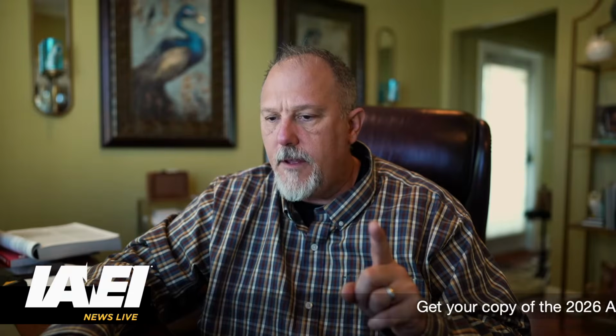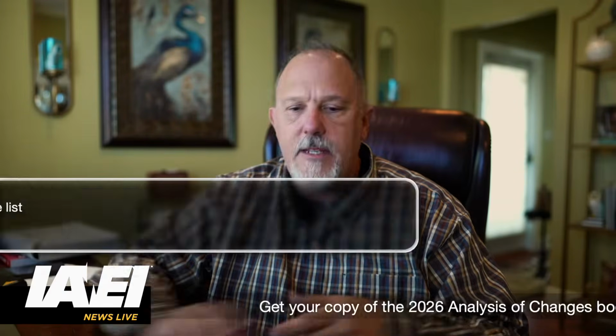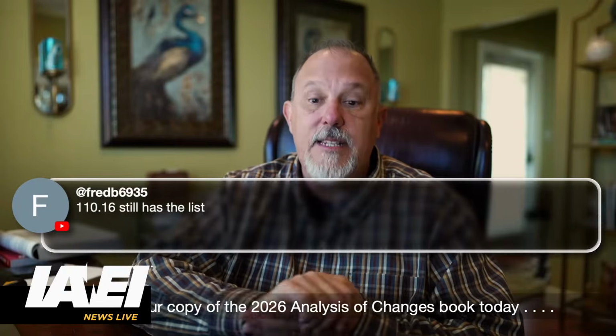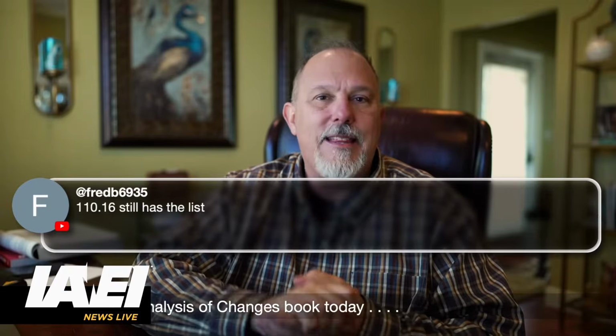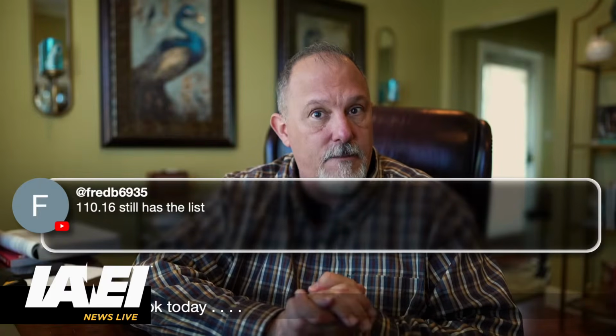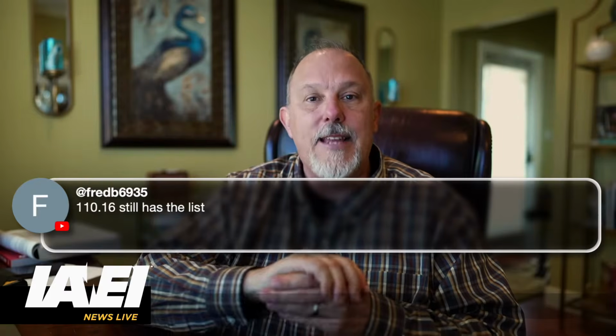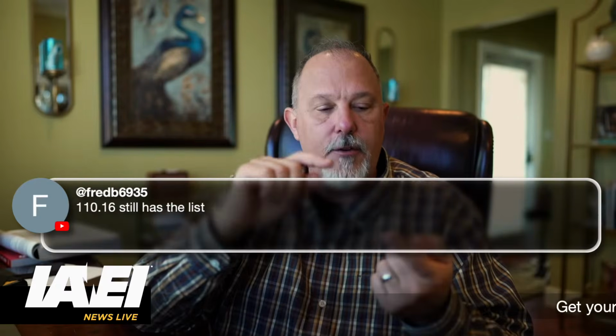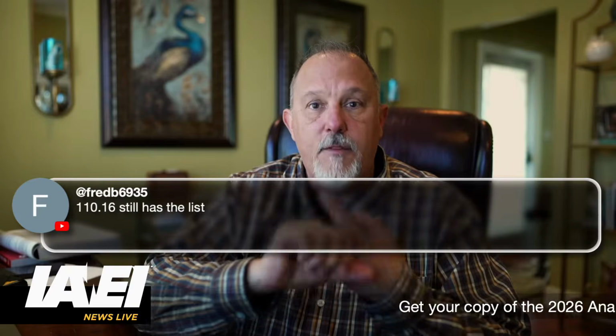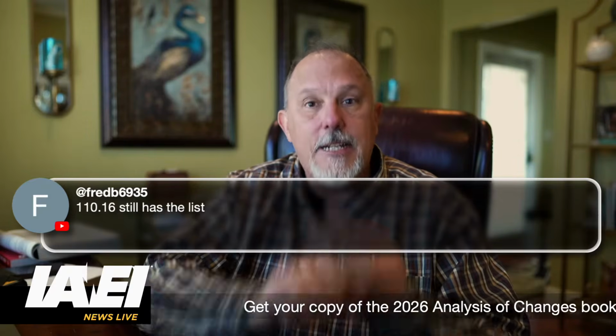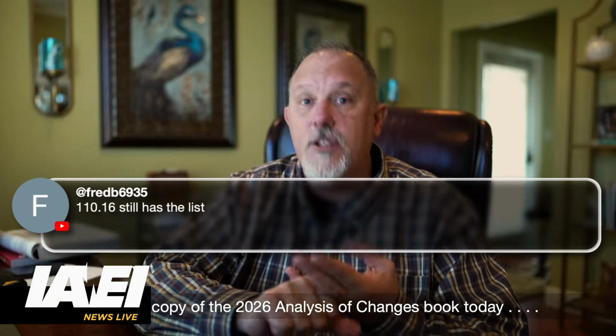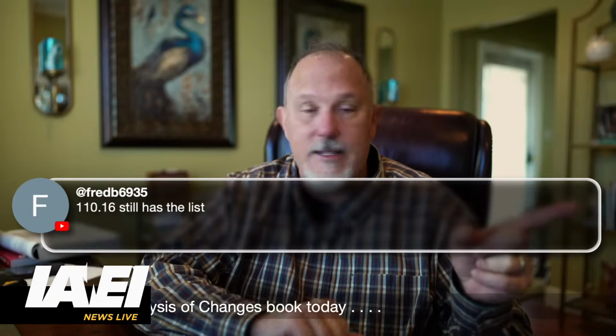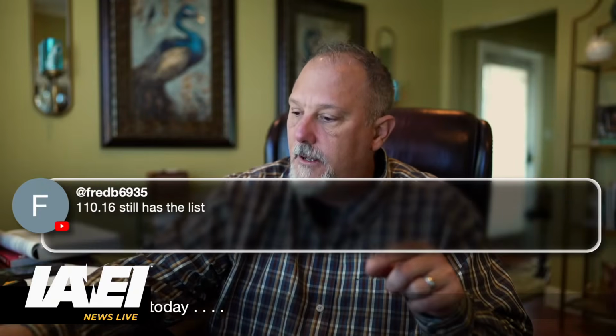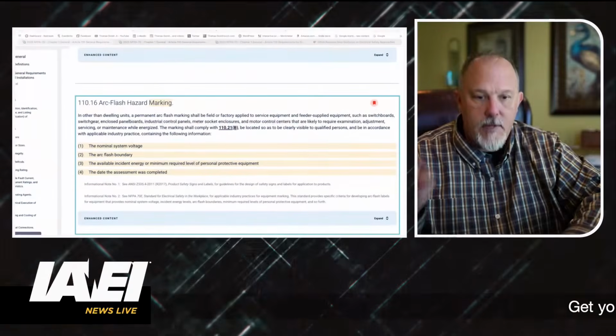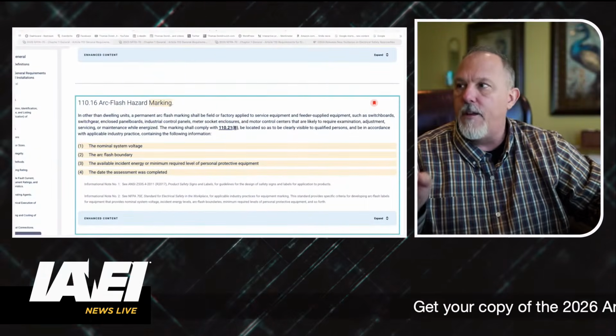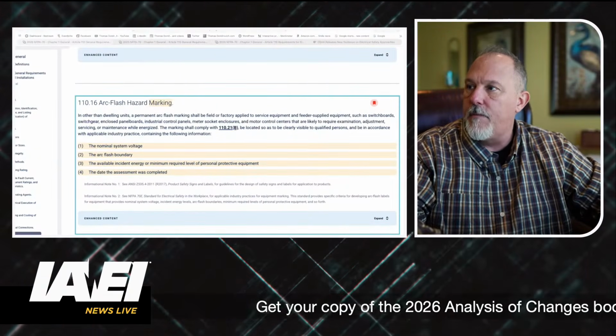This is the requirement. Freddie B says 110.16 still has the list. Now, this is a different list, because the list that was there before just said you needed to know the voltage, the available fault current, and the clearing time of the service disconnecting means. This is much different than those three parameters.